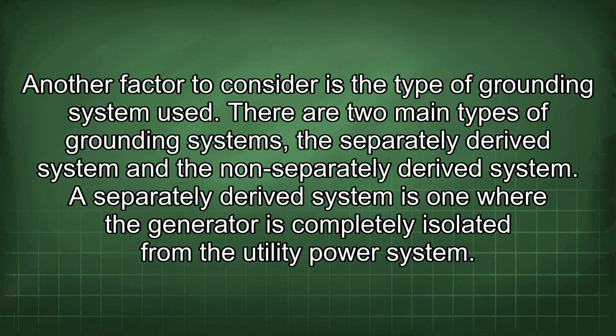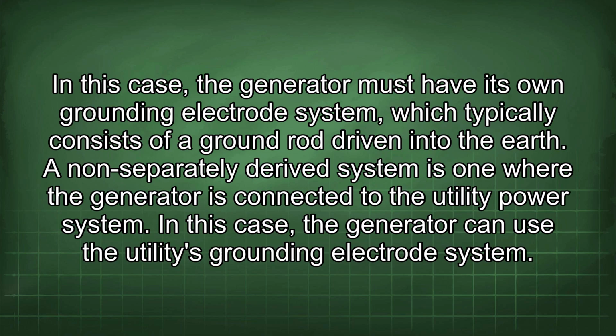Another factor to consider is the type of grounding system used. There are two main types of grounding systems: the separately derived system and the non-separately derived system. A separately derived system is one where the generator is completely isolated from the utility power system. In this case, the generator must have its own grounding electrode system, which typically consists of a ground rod driven into the earth. A non-separately derived system is one where the generator is connected to the utility power system. In this case, the generator can use the utility's grounding electrode system.